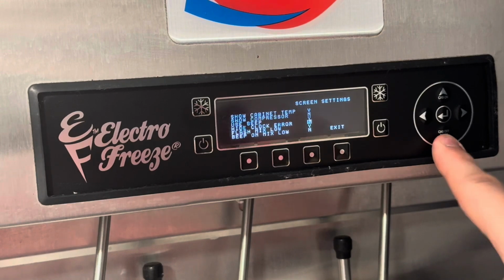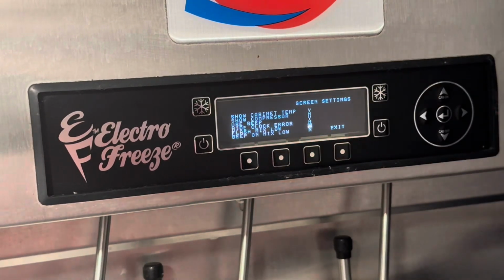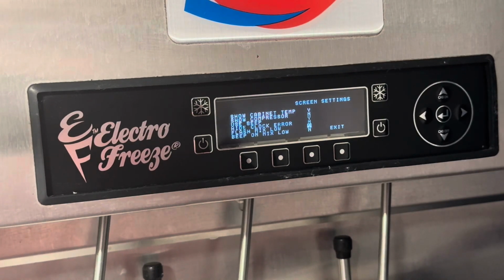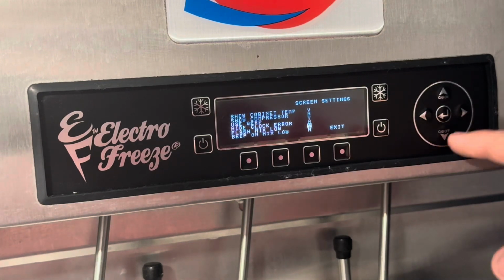Use clock error, no. Flash mix low, you can make it flash on the screen saying mix low. You can set that to yes or no. I would advise keeping it on, that way you'll be alerted when your mix is low. Otherwise you can start running air into the machine and create problems with the consistency of the ice cream coming out.